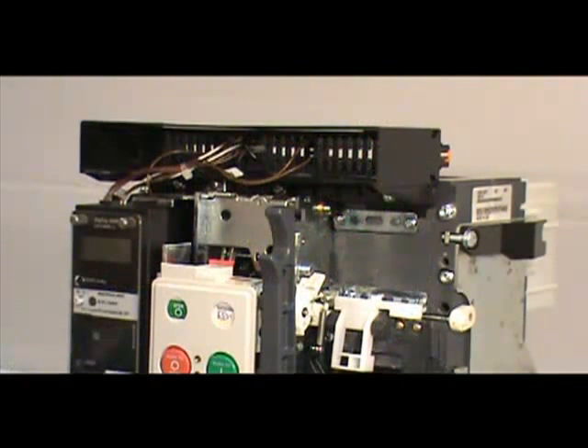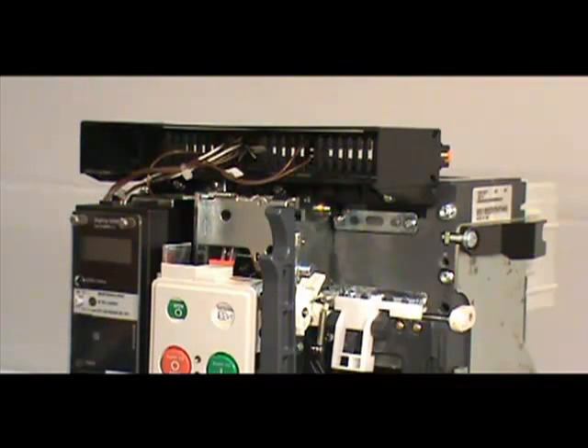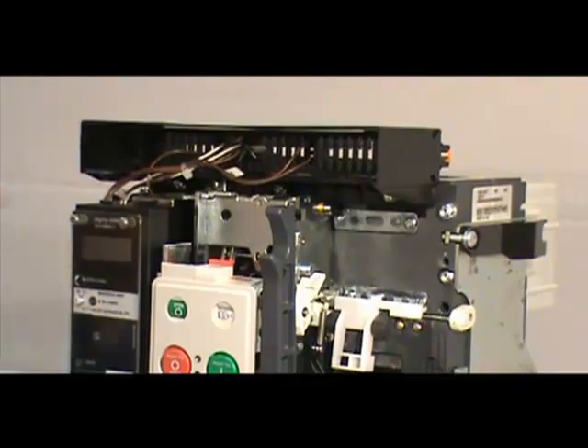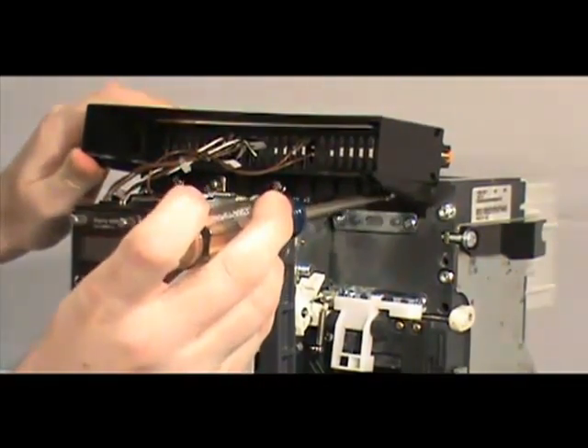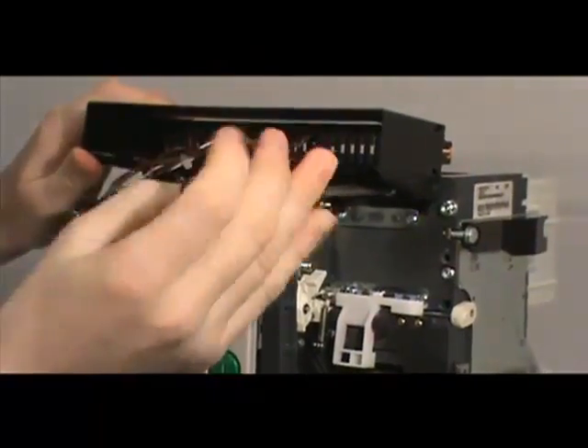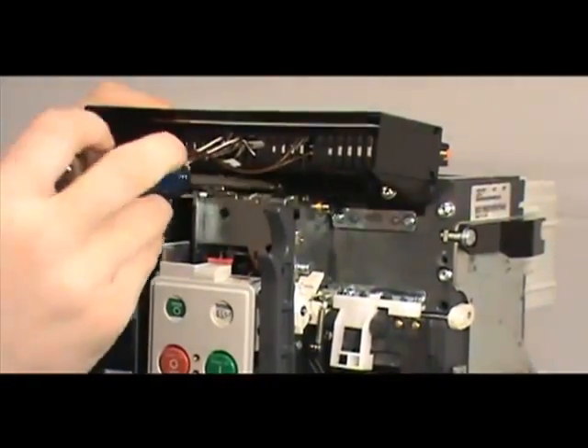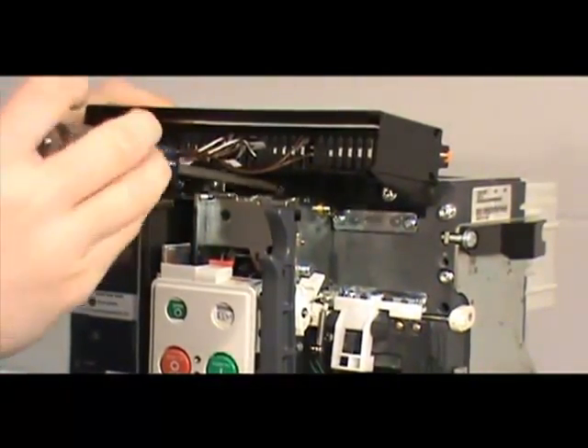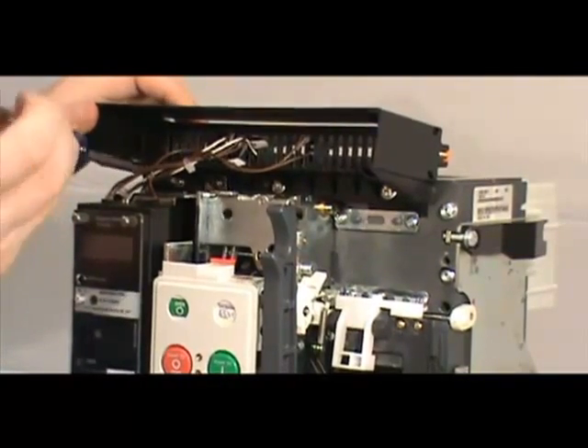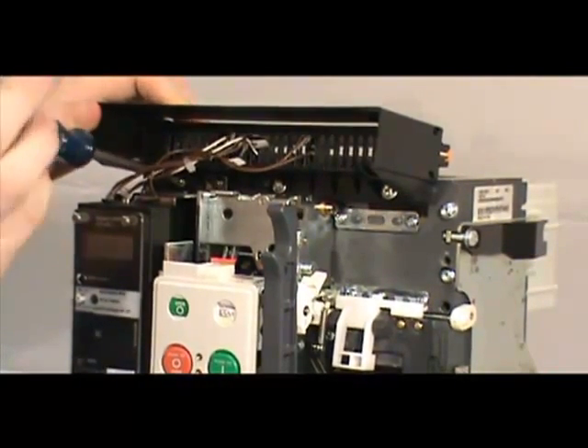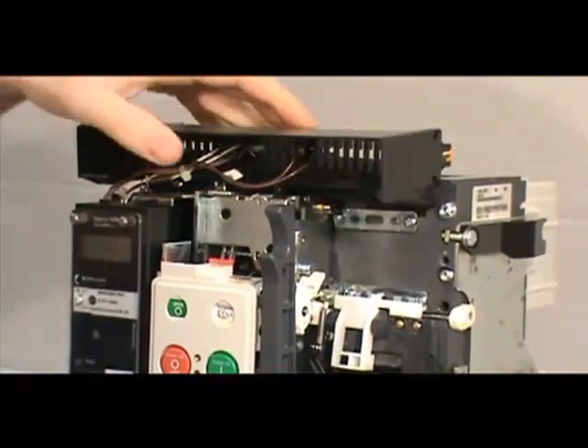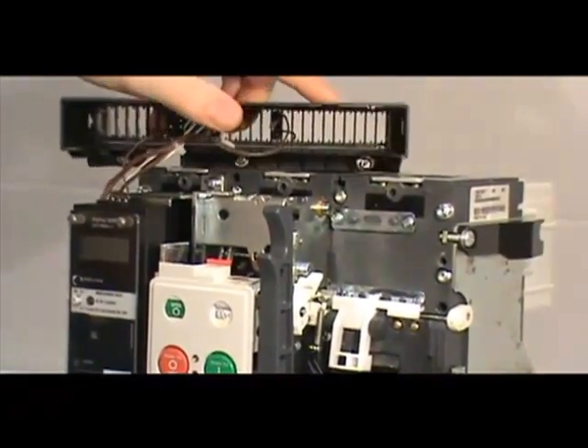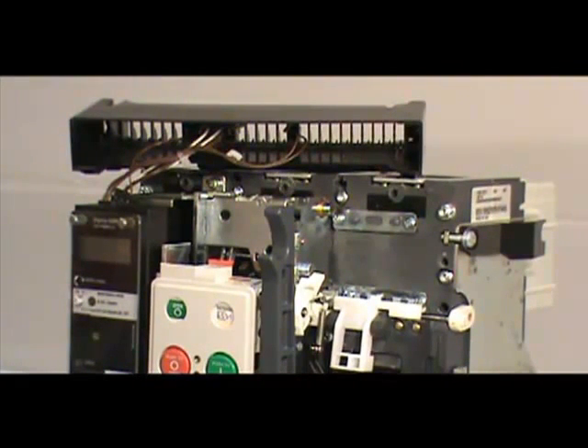The secondary mounting bracket, which is located at the top of the breaker, must be loosened in order to access the key lock mounting location. To do this, you must locate the three screws that hold the mounting bracket in place and remove them with the number two phillips head screwdriver. You do not need to remove any wires or connectors in order to move the secondary mounting bracket.